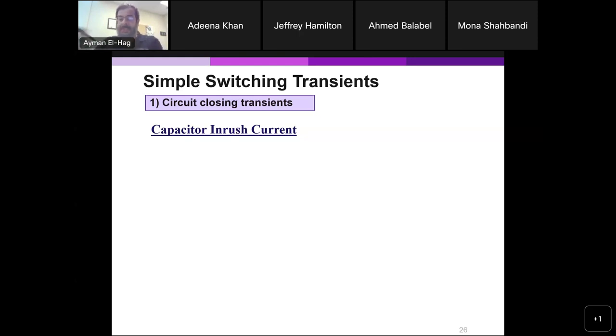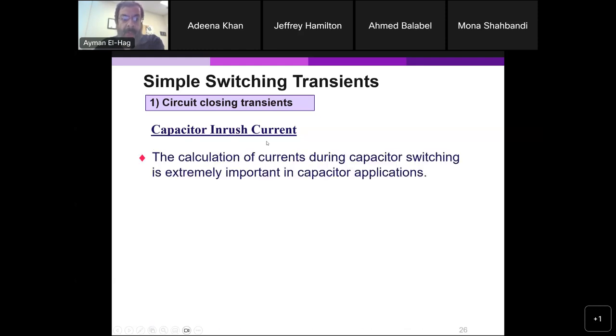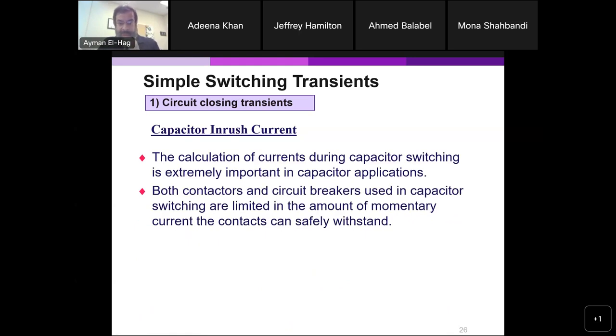As I mentioned before, we talk about two events. We talk about capacitor inrush current. This is under circuit-closing transients. When I close a circuit, the example I will take here is the capacitor inrush current. Now, how do we calculate this huge current that will result in an overvoltage? It's very, very complicated. We want to show you a simple way to do the calculations to get some idea about it, and then we have to do a lot of approximations.